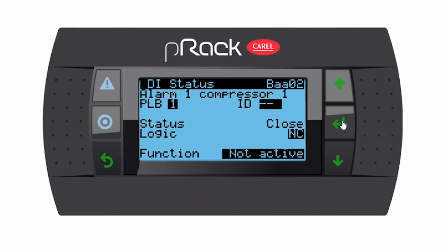Alarm 1, compressor 1. Remember, yes, we do have one because the note said 1 alarm per compressor, and I'm going to assign them. Compressor 1 will be 1, 2 will be 2, 3 and 4 and so forth. It's going to be normally closed. So let's go down to compressor number 2, alarm 1 for compressor 2, and we're going to make it a 2 and enter. It's going to be normally closed logic. It's perfect. Enter and go down. Alarm 1 for compressor 3. Let's assign it to number 3. It's going to be normally closed as well. Let's go down to compressor number 4. Make that a 4. Normally closed. Perfect.